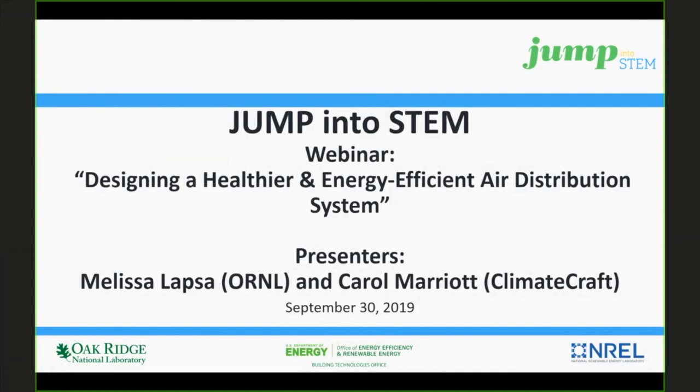There can be. It depends on where your DOAS is located. If you are in a heating-dominated climate, you probably would include a heating coil. But if you had a DOAS system, the energy recovery wheel would probably take care of most of your heating requirements, in which case you probably wouldn't have a heating coil. You may also have, instead of a heating coil, a hot water coil.